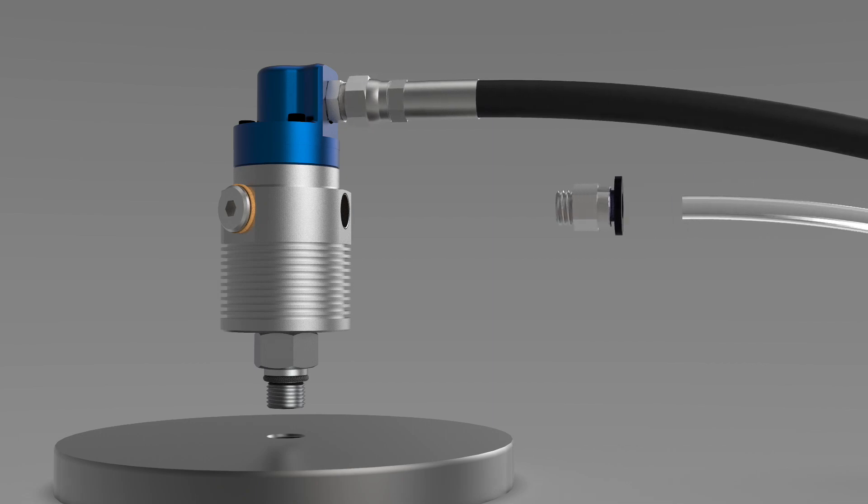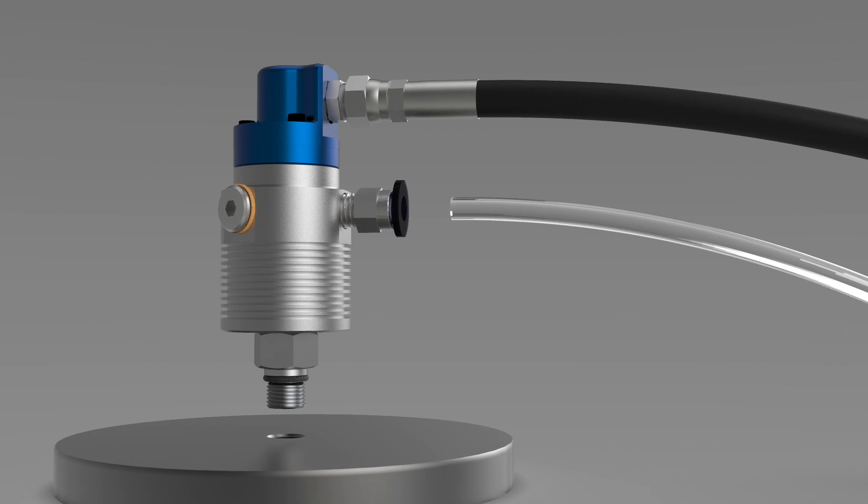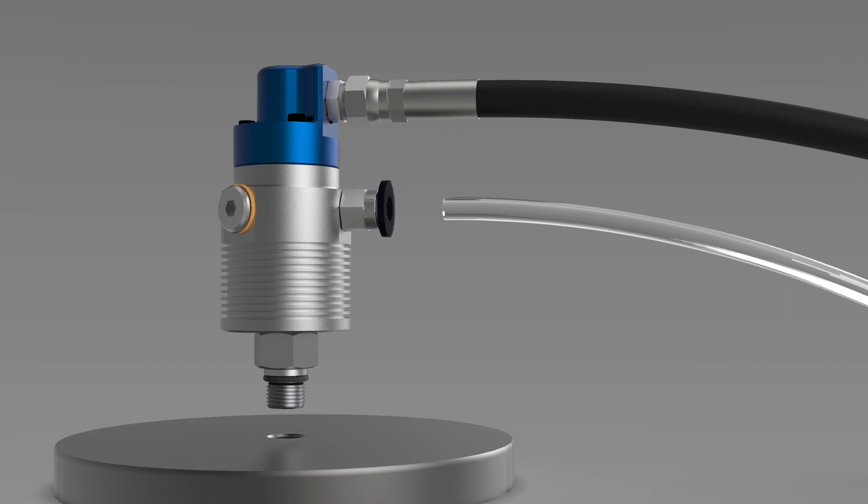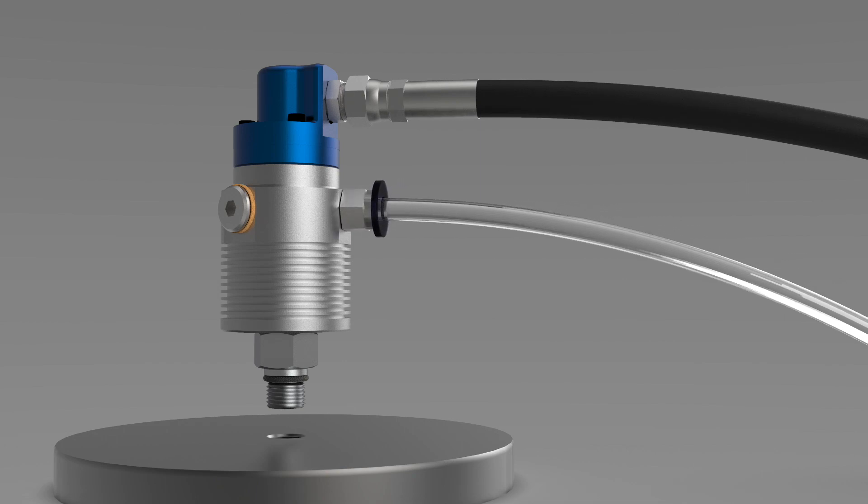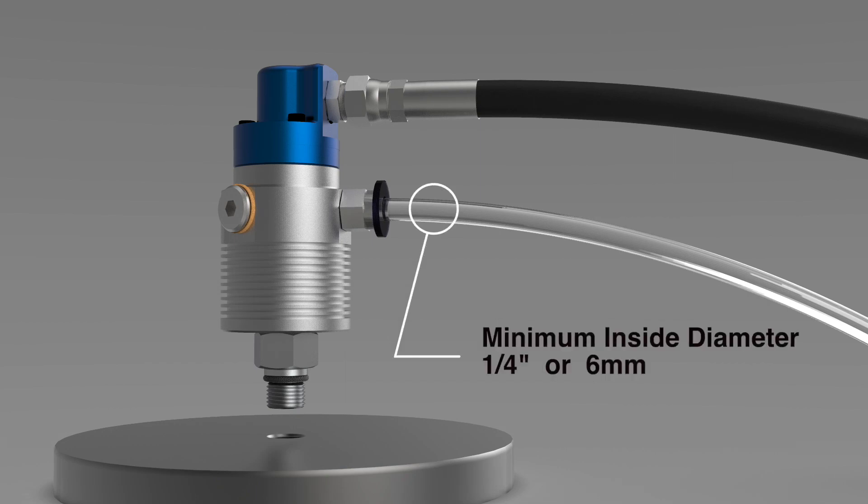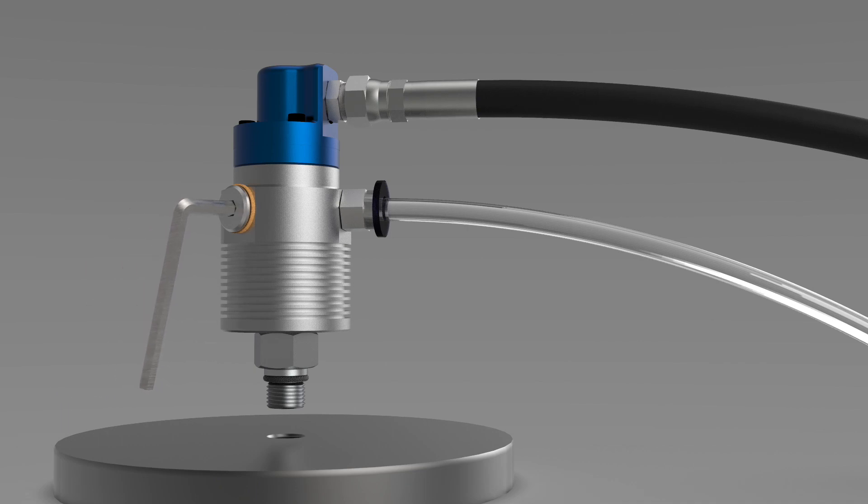Step 2, connect the drain hose to the union. Note that the minimum inside diameter for the drain line is about 1 quarter inch or about 6 millimeters. Check to see that any supplied drain plugs are tight enough to seal.